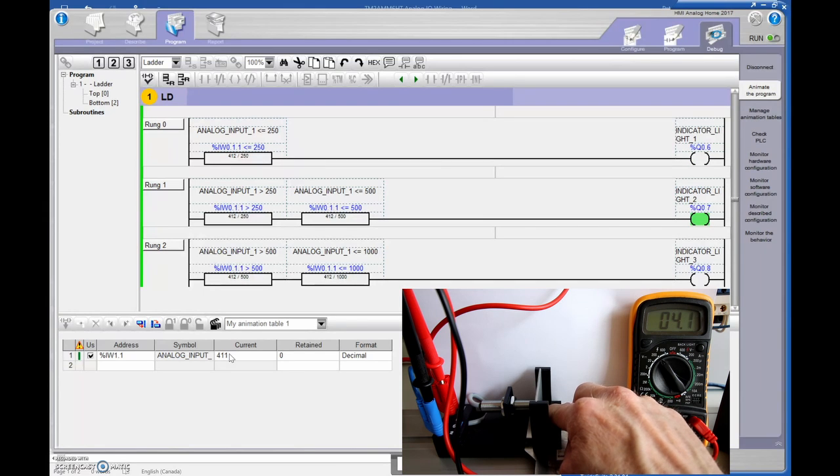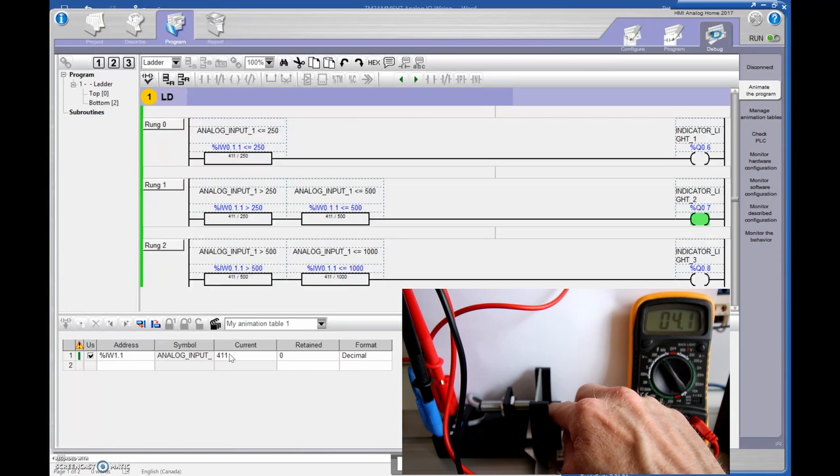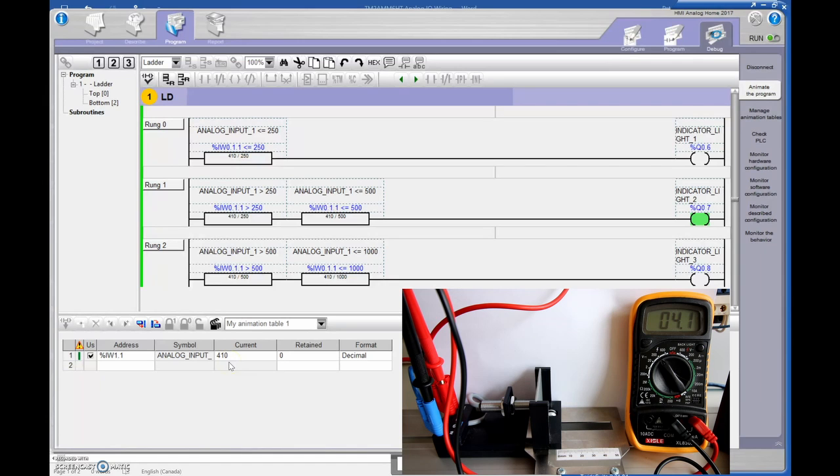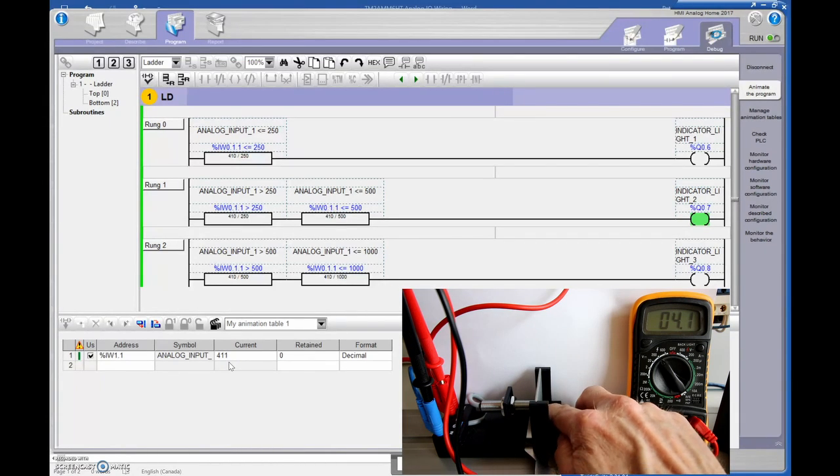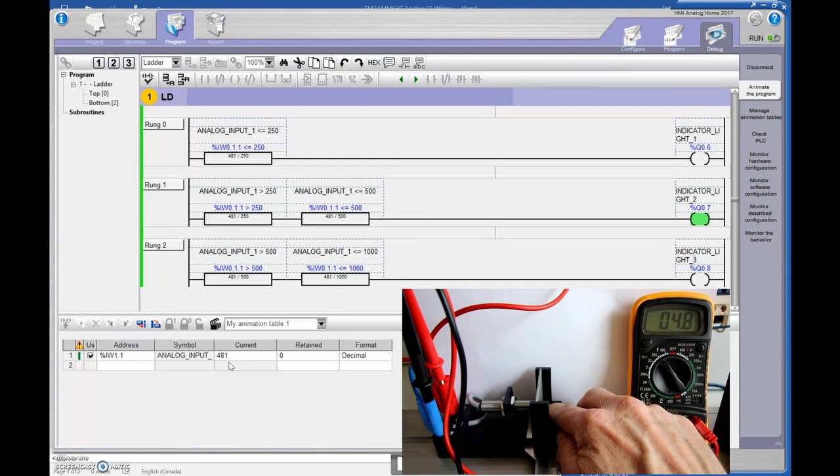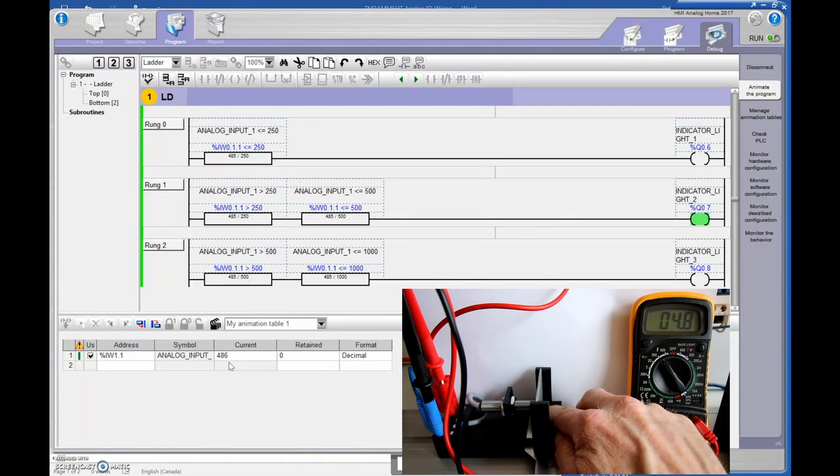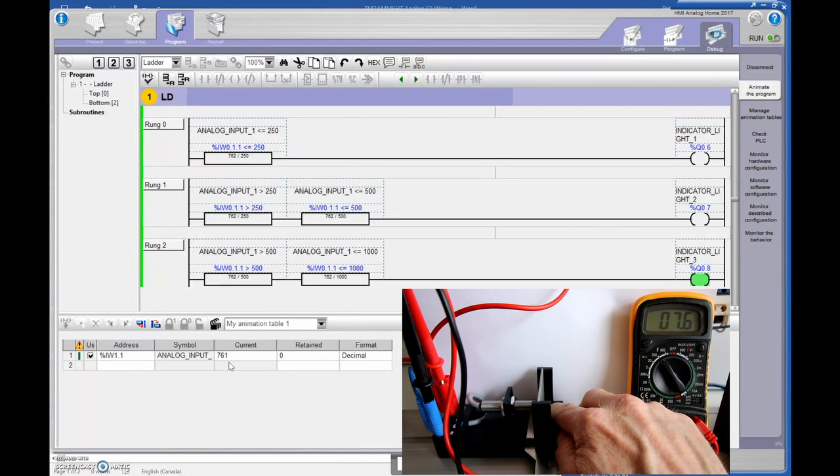What do we have? 4.11, 411 on the PLC. So remember that my range is from zero to a thousand. So that this value here matches exactly with what the meter is showing. I'm now going to go above five volts. So we're climbing in value, right? 4.5, 4.8. Right. You can see that exact value on the PLC there. And then when I go above five volts, the third light is going to turn on. Beautiful. 7.6. Awesome. Very cool. Going up to nine volts now.